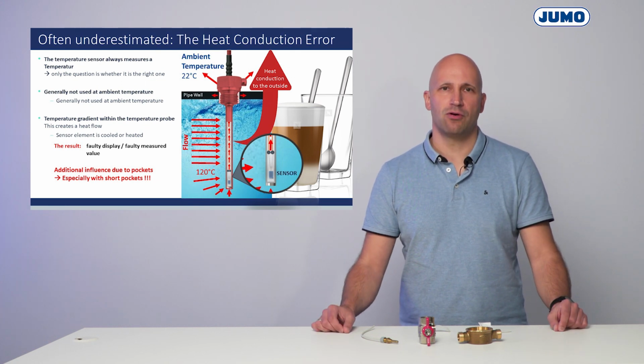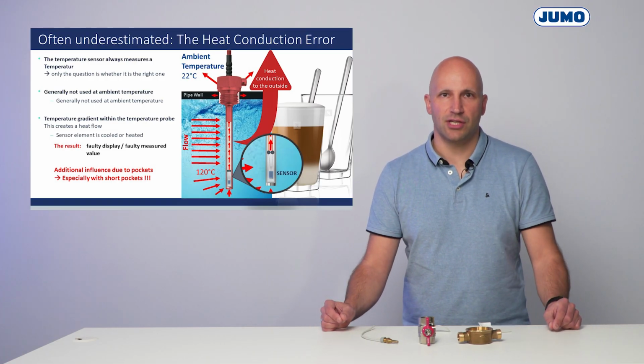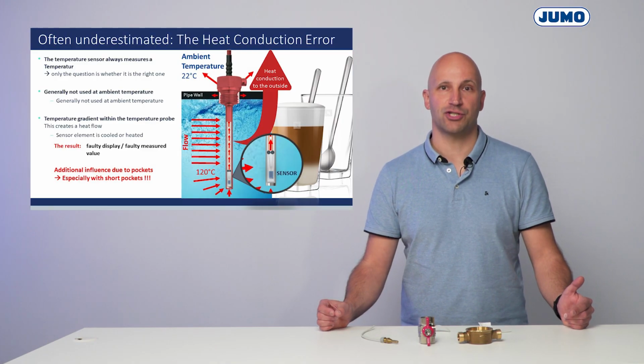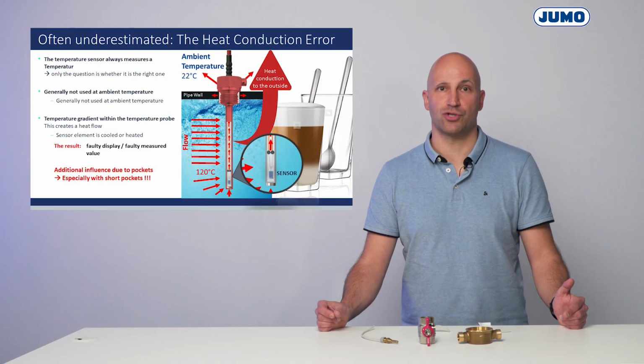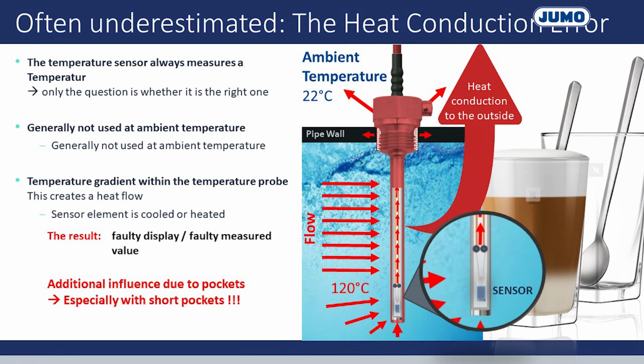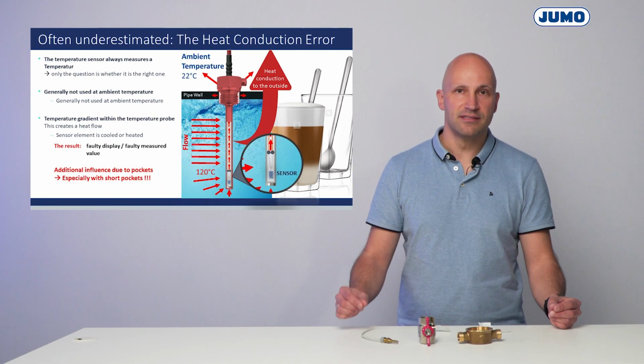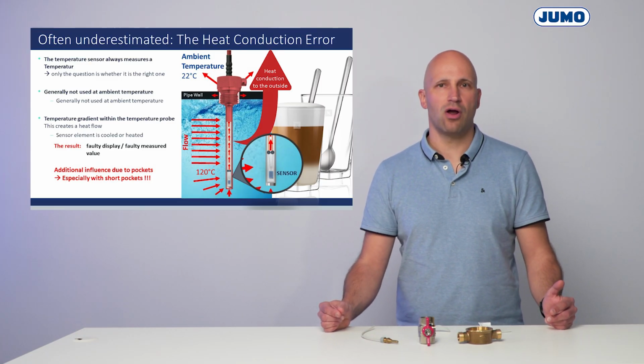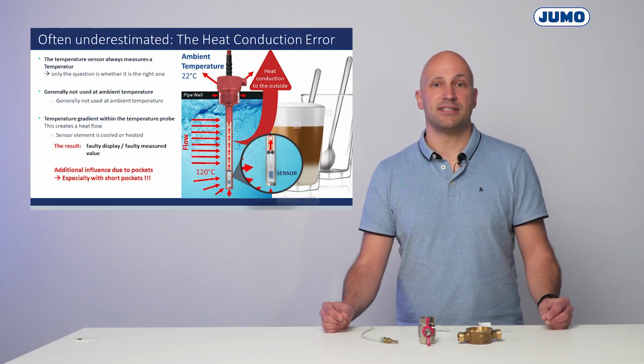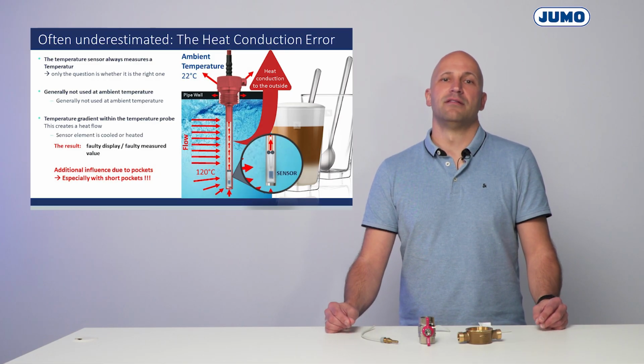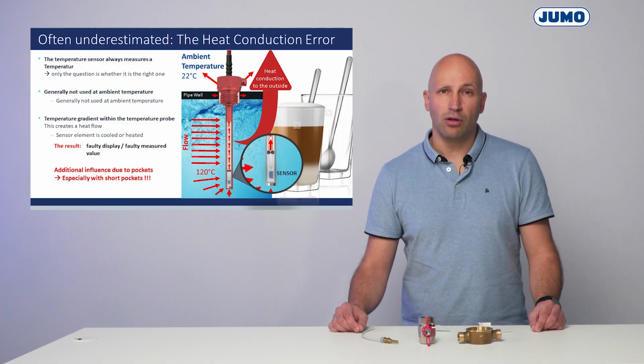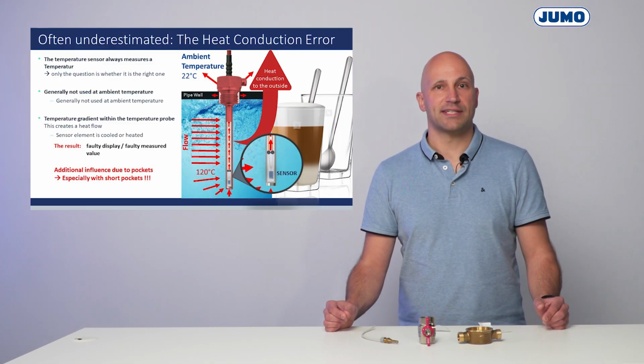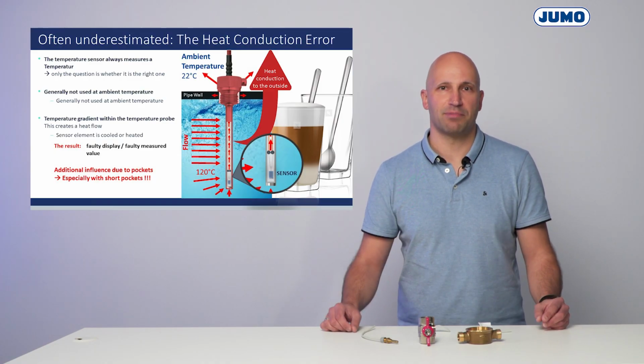Let's imagine that a temperature probe measures a temperature, but due to incorrect installation or external influences, it does not measure the temperature of the medium, but a different or incorrect temperature. The problem occurs particularly when there is a large delta between the measured temperature and the ambient temperature. A temperature gradient then occurs within the sensor, causing a heat flow. The sensor element is therefore either heated or cooled, and this means that the sensor no longer measures the actual temperature of the medium, but instead displays falsified values. This effect is not just a minor problem.